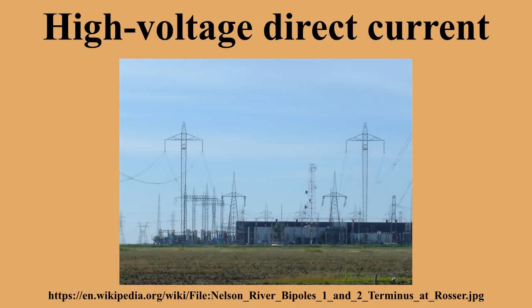They have extended the use of HVDC down to blocks as small as a few tens of megawatts and lines as short as a few score kilometers of overhead line. There are several different variants of VSC technology. Most installations built until 2012 use pulse width modulation in a circuit that is effectively an ultra-high voltage motor drive. Current installations, including HVDC PLUS and HVDC MaxSine, are based on variants of a converter called a modular multi-level converter. Multi-level converters have the advantage that they allow harmonic filtering equipment to be reduced or eliminated altogether.